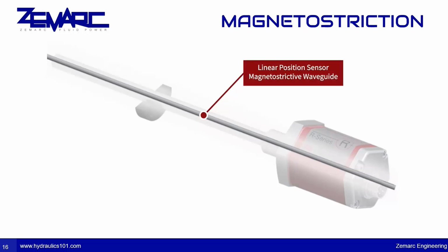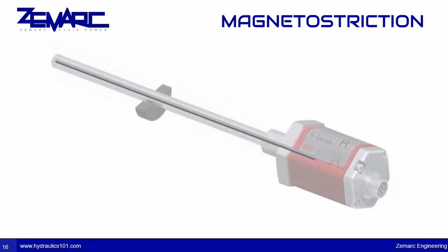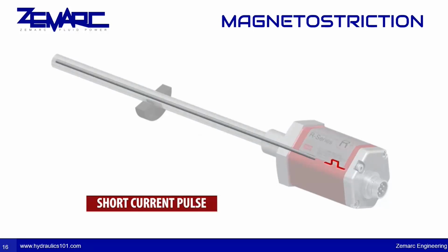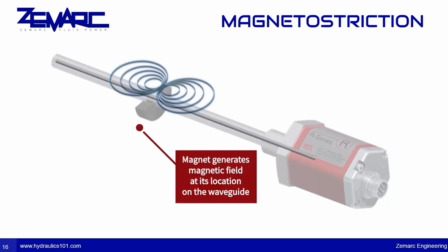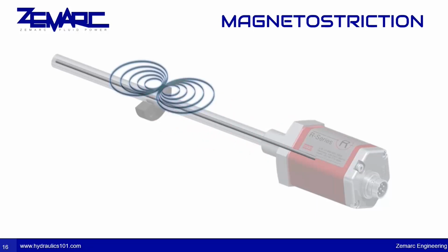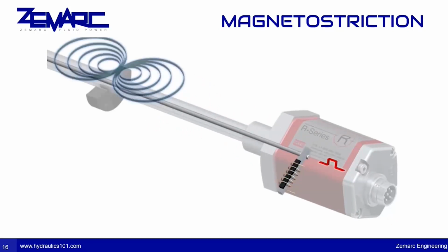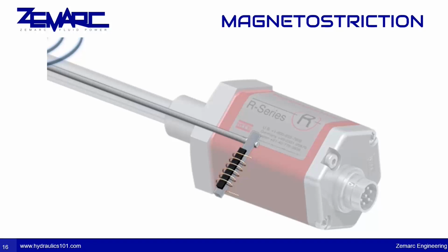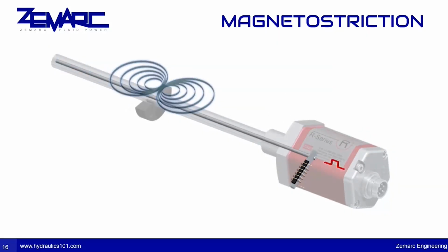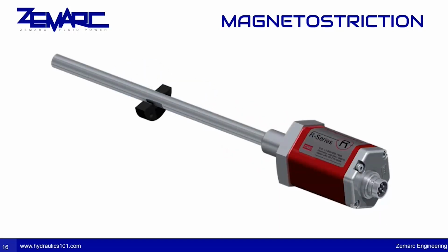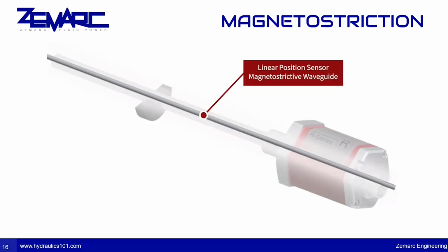Linear position sensors utilize the properties offered by a specially designed magnetostrictive waveguide. A short current pulse generated by the sensor element is sent through the waveguide, and this creates a momentary radial magnetic field. A magnet connected to the object in motion generates a magnetic field at its location on the waveguide, and the momentary interaction of the magnetic fields releases a torsional strain pulse that propagates the length of the waveguide. This ultrasonic pulse is processed by the sensor electronics and converted into an electrical signal. The speed of the ultrasonic wave is precisely known, so the time to receive the wave pulse is converted into a highly accurate linear position measurement.